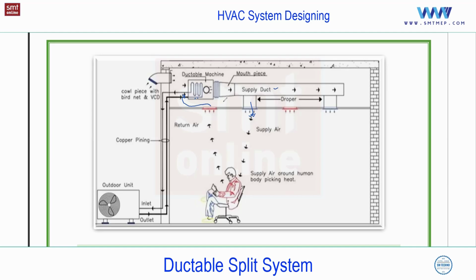So the first point is that the capacity is higher, and if you want we can continue this duct. You see, this is, say, space 1. I can continue to space 2, or I can continue this to space 3 as per the required capacity. For example, 5 spaces, with a total requirement of, say, 10 TR. As per load calculation, I'll go for the 10 TR capacity ductable split. And with the duct, I can supply the air to all 5 spaces. But remember, 1 AHU means 1 thermostat, 1 control. So the number of spaces is 5, but the zone is going to be 1, because there is only 1 thermostat, na?